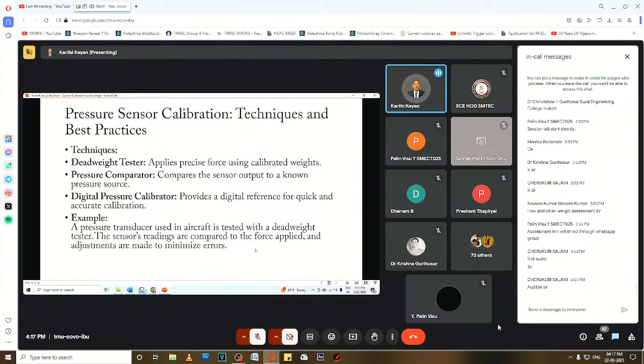Next one is pressure sensor calibration. For pressure sensors, three kinds of methods are used: dead weight tester, pressure comparator, and digital pressure calibrator. A dead weight tester applies precise force using a calibrated weight. Calibrated weight means it is already a measured weight. If it shows the precise force, it will be a perfect one. Next, pressure comparators compare the sensor output to a known pressure source.